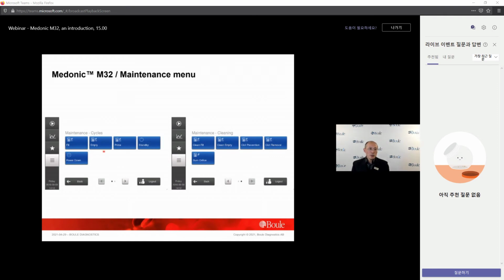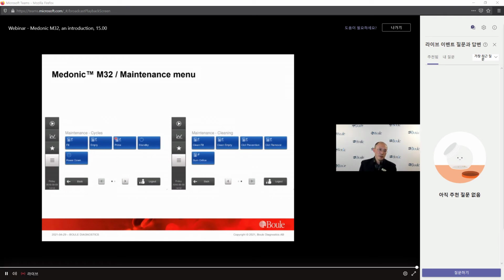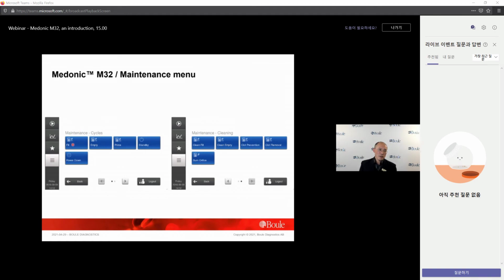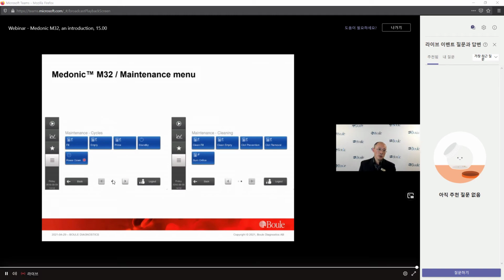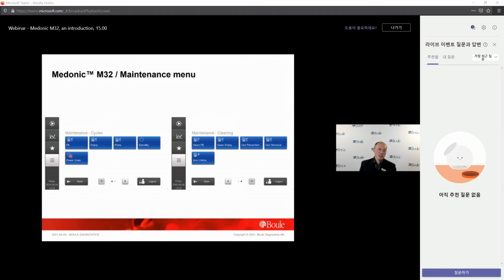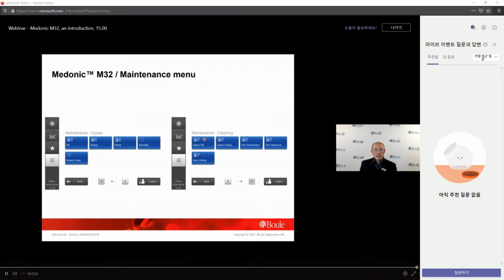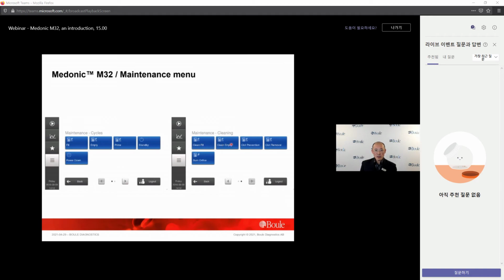The maintenance menu has 2 pages. The first is to run fill or empty of reagent, to do prime, to get into standby, and to go to the power down procedure. We will specify this power down procedure because there are related problems. We will see shortly. The difference between the maintenance cleaning, clean fill and clean empty, and the normal fill and empty, is the reagent level detector.